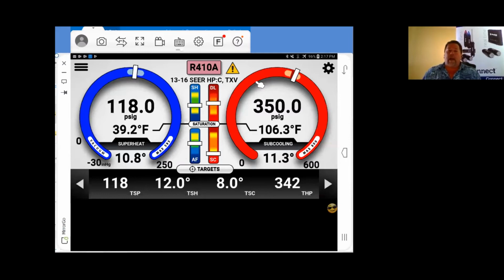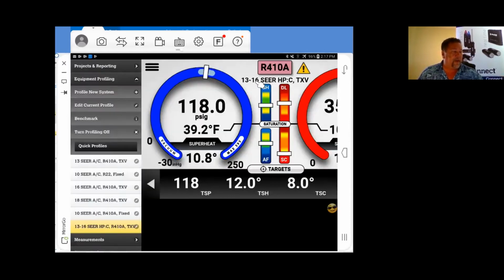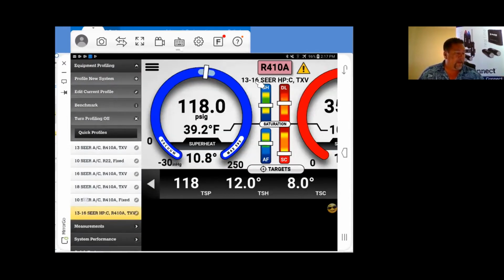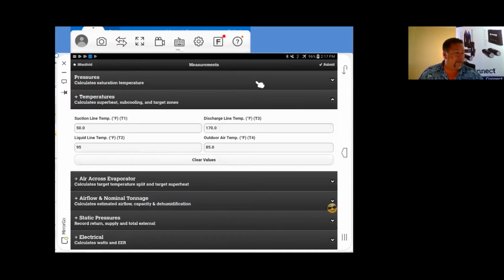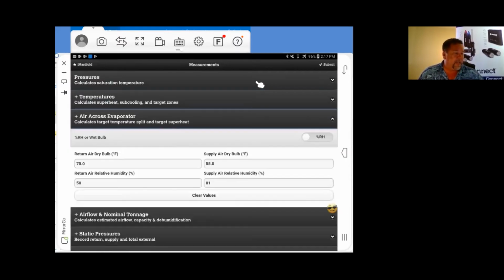So as a lot of people were asking about, they said, how do I use it if I just need to go in and I just want to do standard pressures and temperatures. It'd go the same way that you use your regular analog set of gauges, except you'd have everything right there on your smart device. It's simply power on, low side, high side, suction line, liquid line temperature, pull it up. I'll take the other temperatures out of the equation and show you what we got. Just so you can see how easy it actually is. We're going to take the air side out.